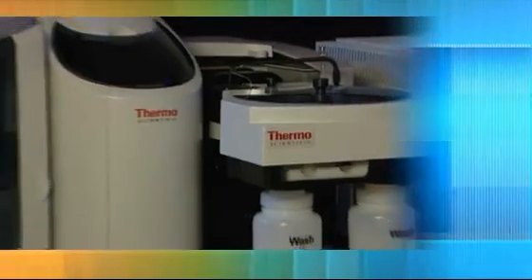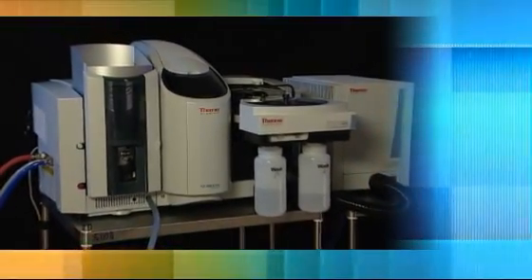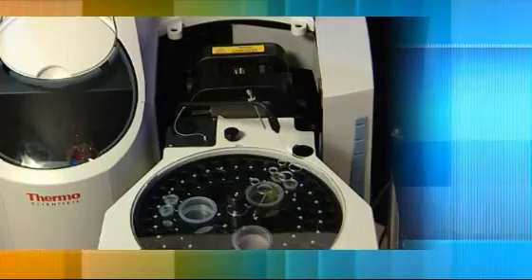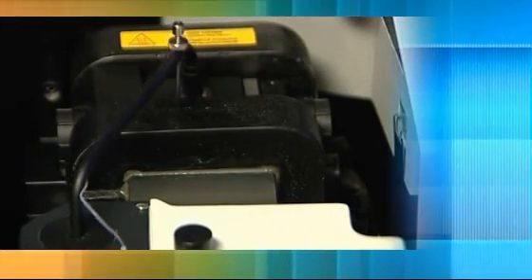During daily setup and for method development, it's essential for the user to be able to see what's happening inside the Graphite Furnace cuvette. Without a clear view of the sample injection, drying, ashing and atomization, it's impossible to optimize a furnace analysis.